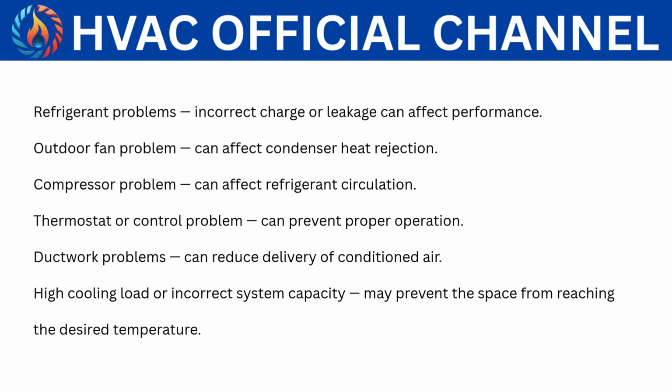Compressor problem can affect refrigerant circulation. Thermostat or control problem can prevent proper operation. Ductwork problems can reduce delivery of conditioned air. High cooling load or incorrect system capacity may prevent the space from reaching the desired temperature.